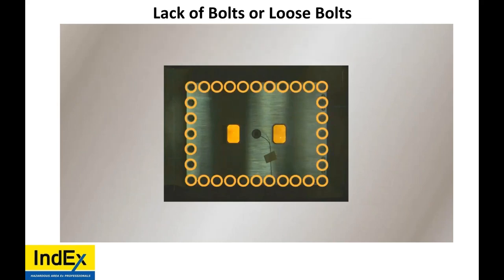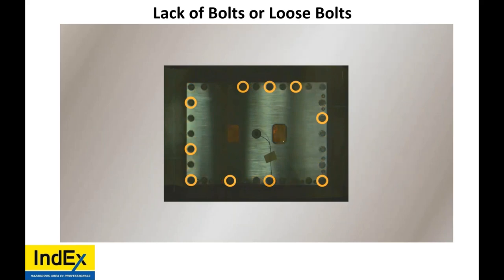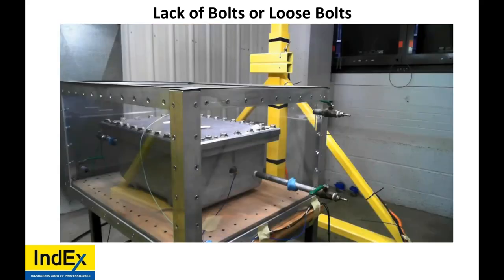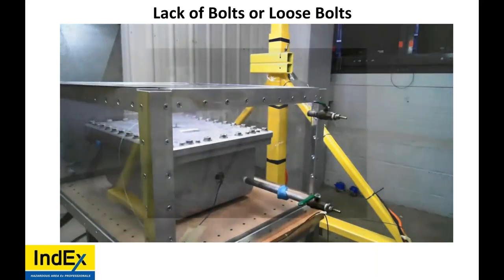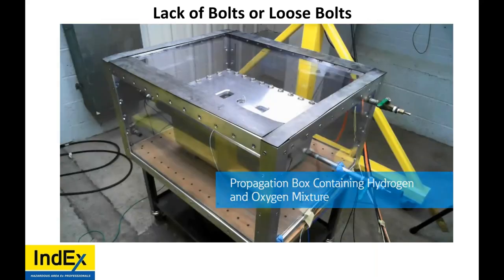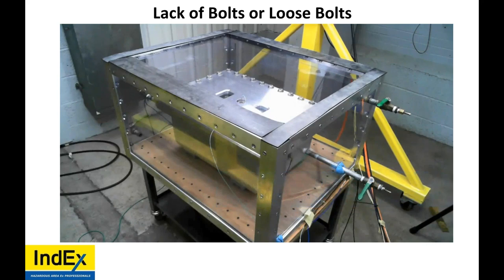So all the bolts are installed, correctly torqued. No scratches. So, that explosion, I don't know if you guys saw it at the end there, happened due to one or two bolts not being installed, or bolts were backed off and not sufficiently torqued.